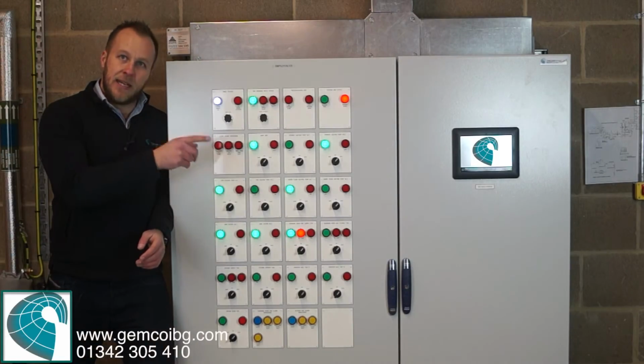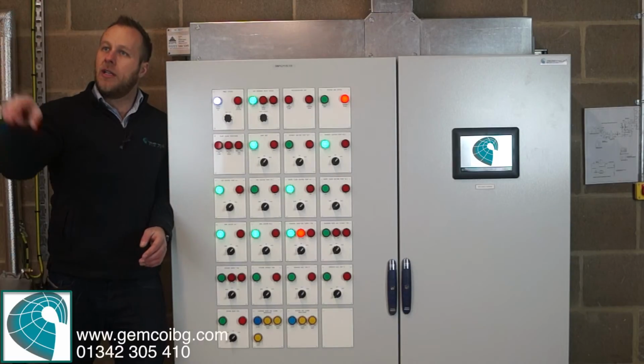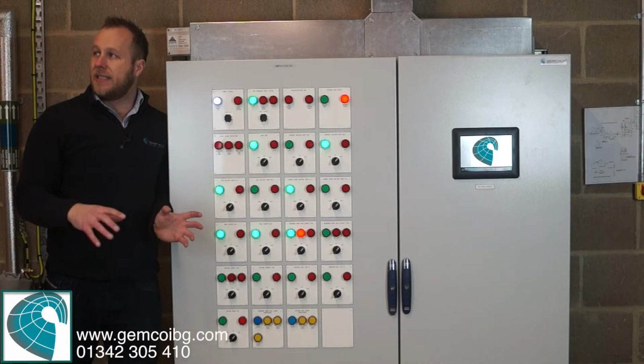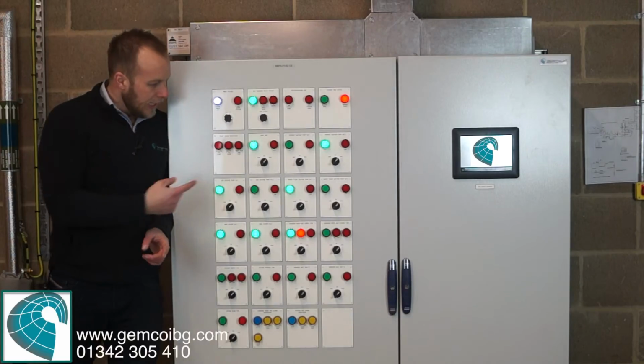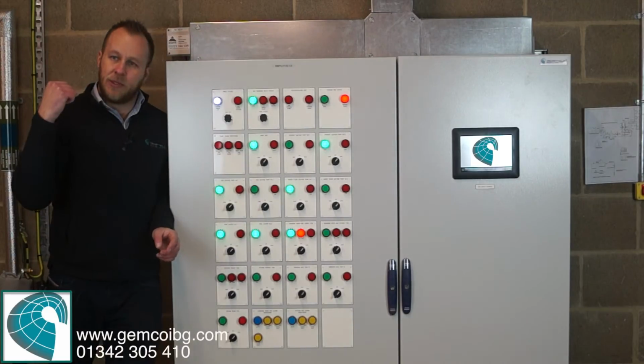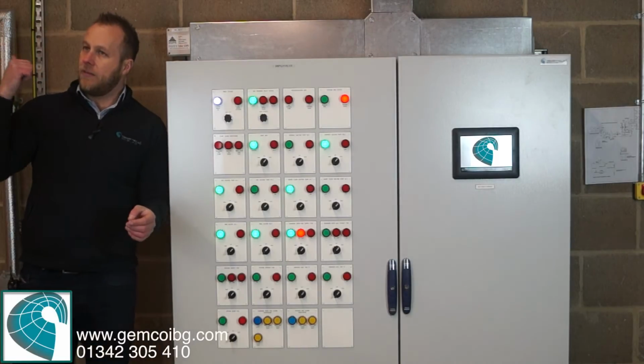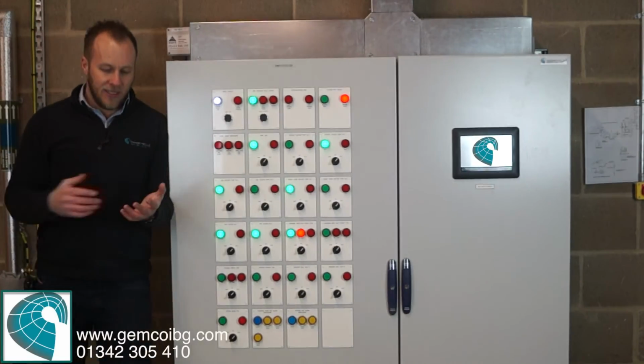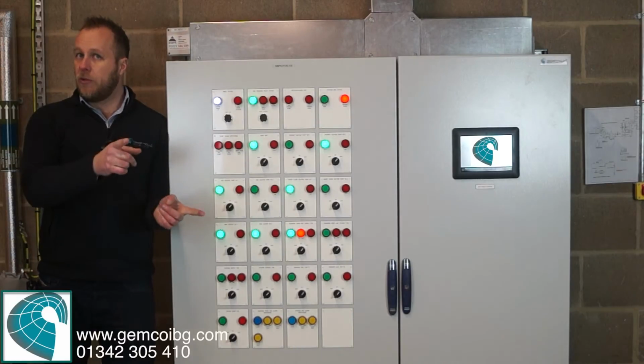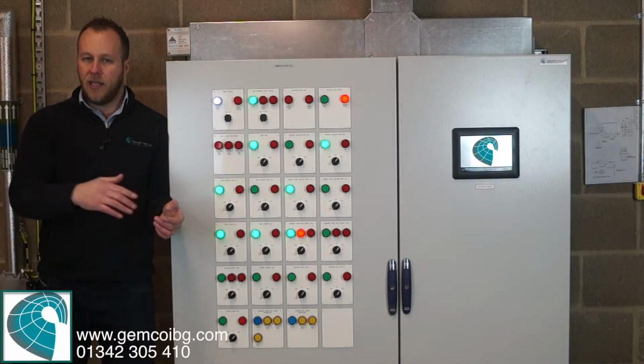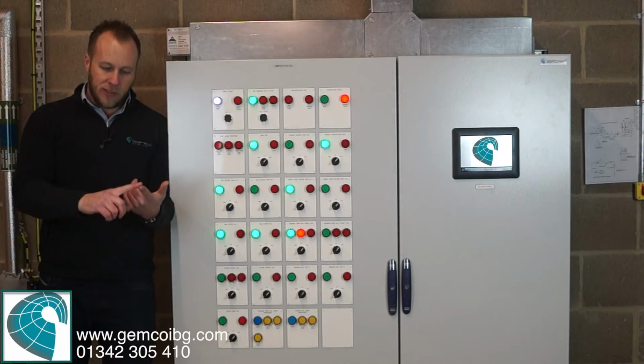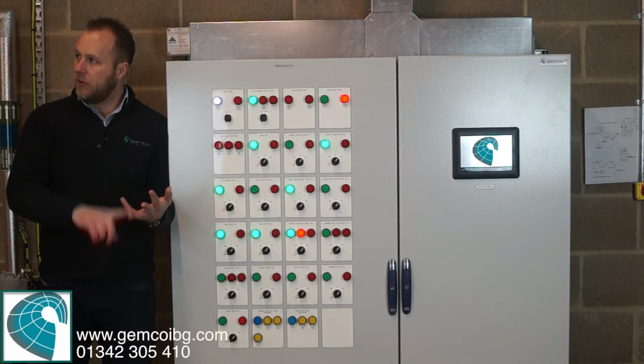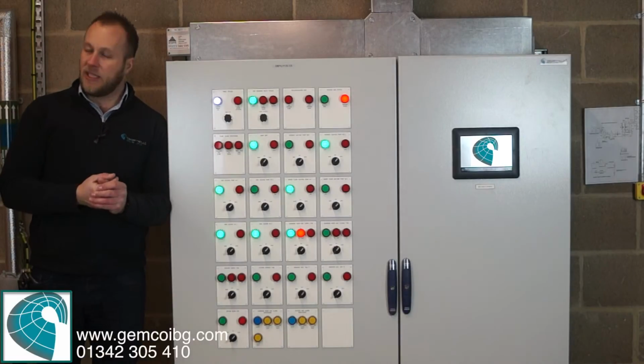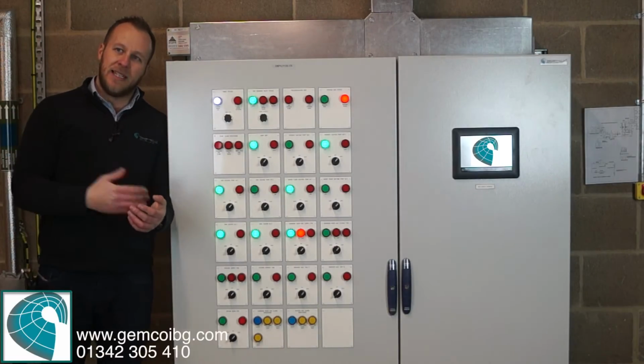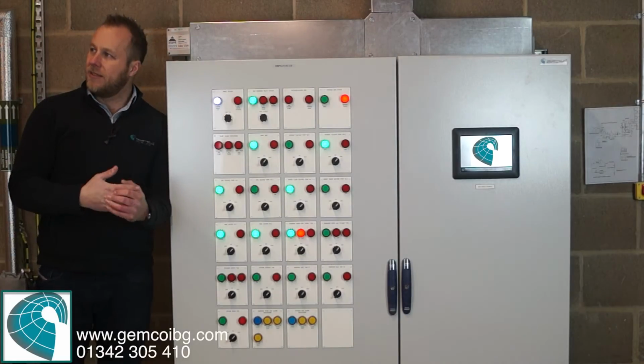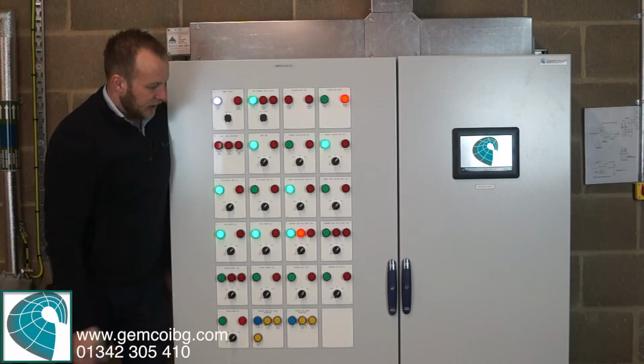The second stage is immersion, so all the sensors in this pipework, we monitor those, and if they go below 16, we run the pumps as well. And the last thing is the space temperature. If the space temperature goes below 16, we just run the pumps, and we run the boilers as well, just to elevate to 20. And the reason for that is for fabric frost. You've got to protect plasterboard, the paint, all of that stuff needs protecting as well, because if you drop anything below sort of 10 degrees in there, you're going to have cracks and all sorts. So there's 3 stages of frost protection built in.